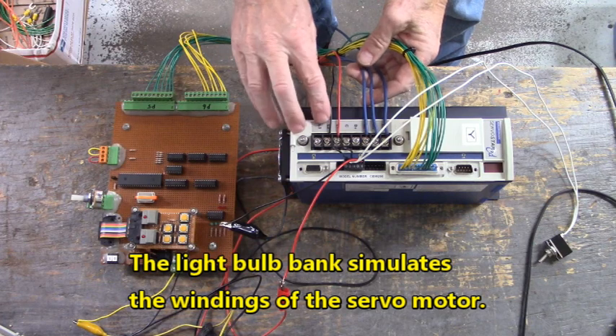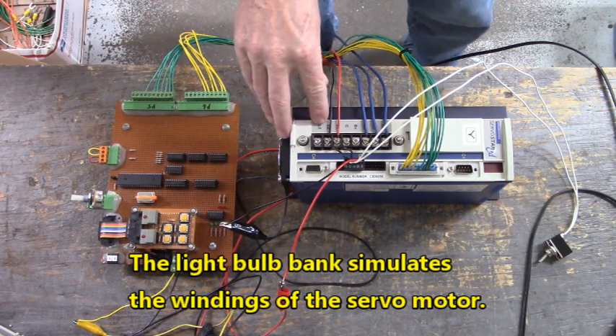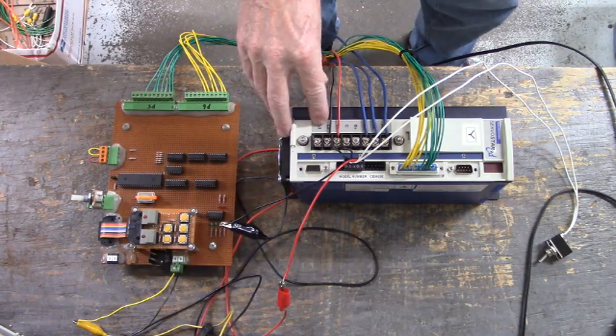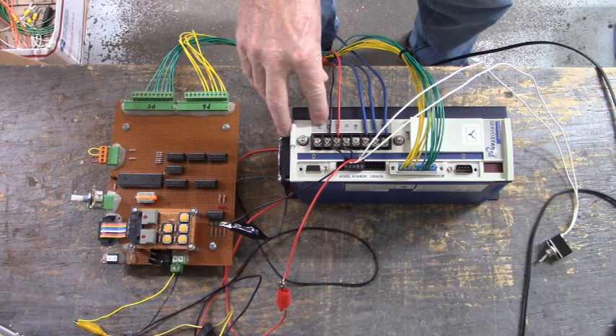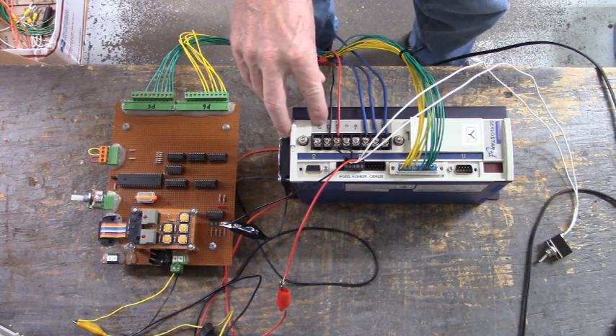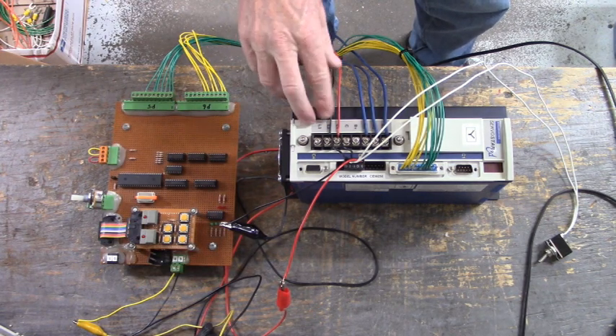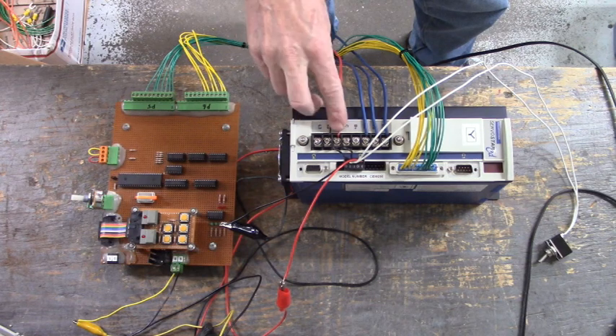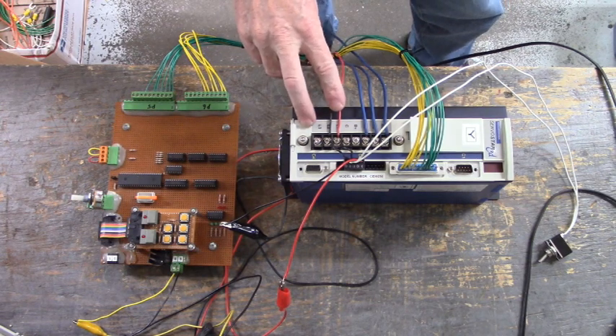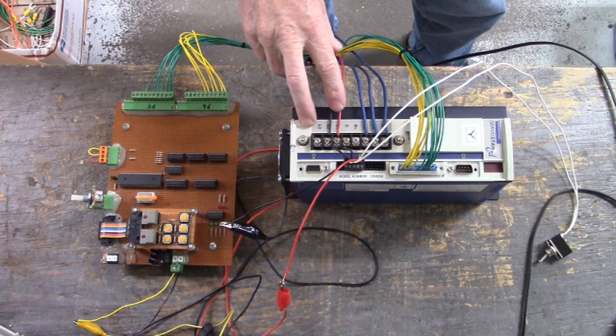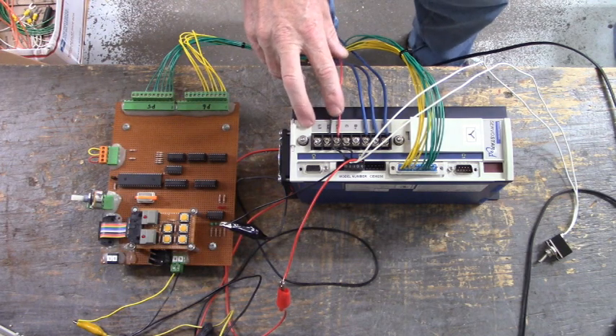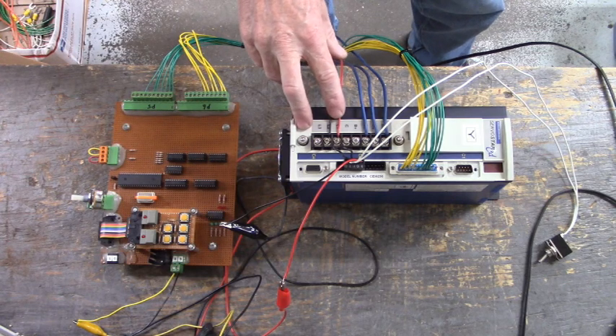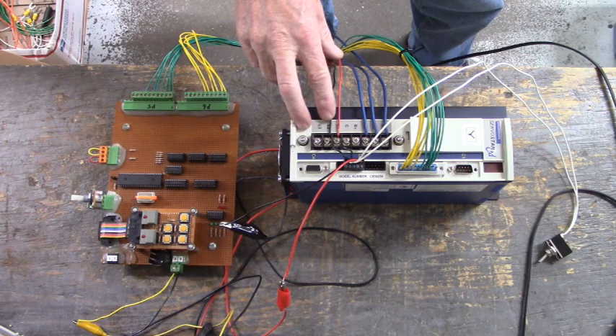Now, L1, L2, and L3 right here, you can either apply 115 volts AC or 230 volts AC, single phase or three phase. And so whenever I have a choice, I always pick the lowest voltage. So I'm going to apply 120 volts AC single phase to L1 and L2.